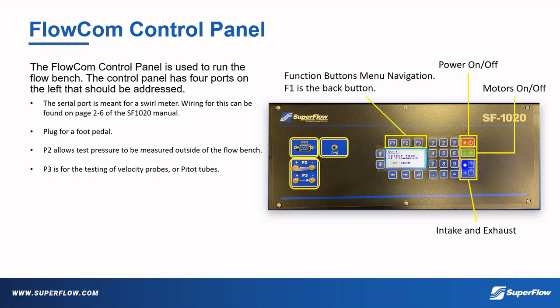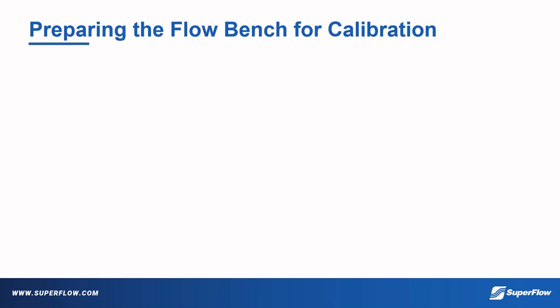The function buttons allow for menu navigation, and anytime you enter into a menu, F1 is the back button. Navigation arrows allow you to navigate through the menus, and the enter key allows you to make selections. What's left is the number pad. These numbers allow you to enter raw data or change the orifice range. In order to prepare the flow bench for calibration, we'll need to reset a few default settings.